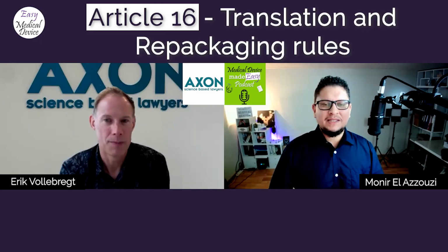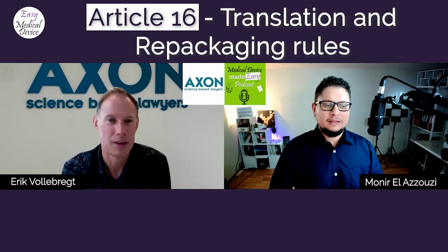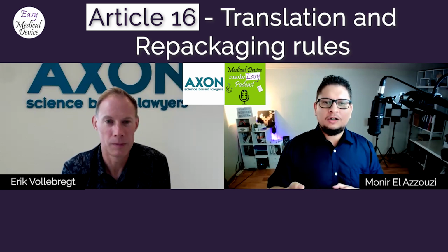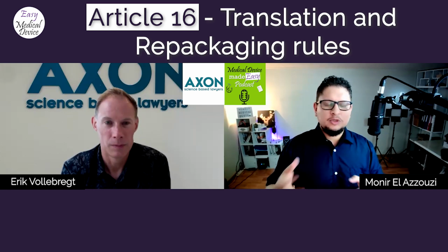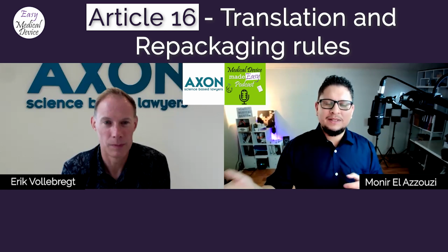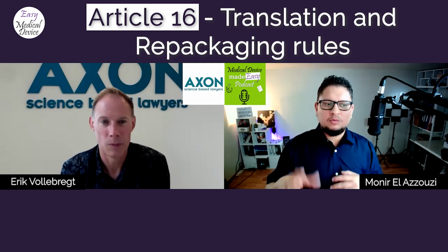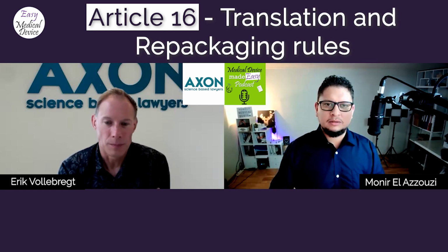As soon as we are willing to do this activity of repackaging or relabeling, it's marked also in Article 16.4 that you have to contact your notified body or competent authority 28 days prior to do this activity. Yes. So does it mean that first you are certified and then you can do this activity, and each time you do this activity, you inform the authorities? Or you can continue to do your business, but if you plan to do this kind of relabeling or repackaging, then you need to get this certificate, you need to get all that. So what is exactly the point here?